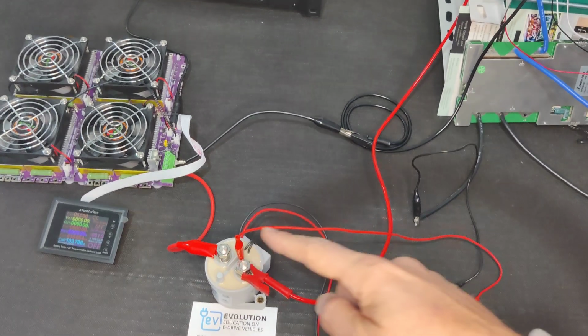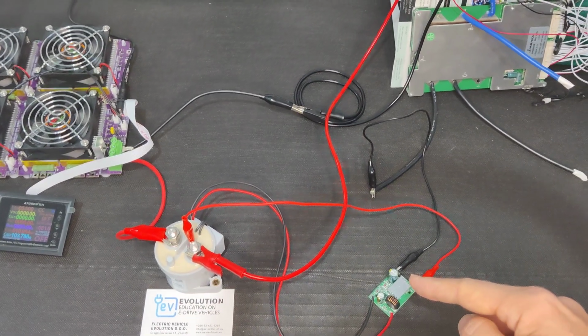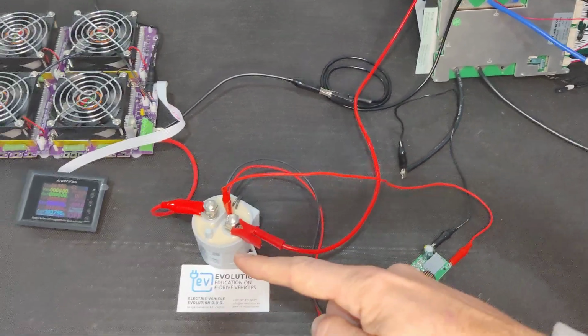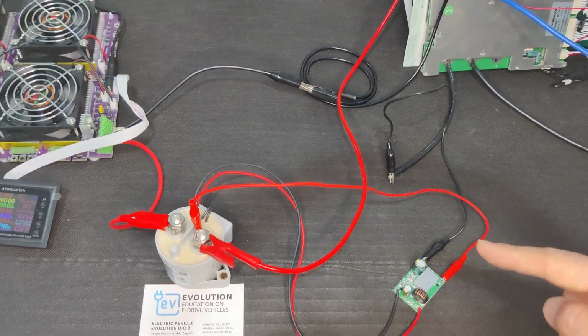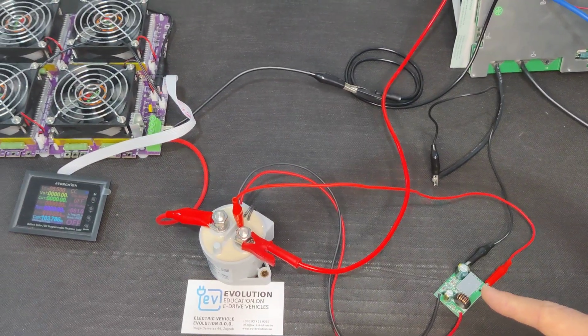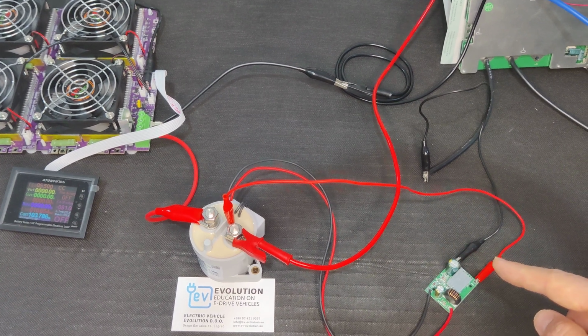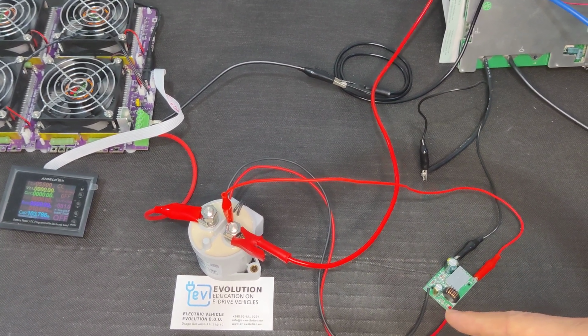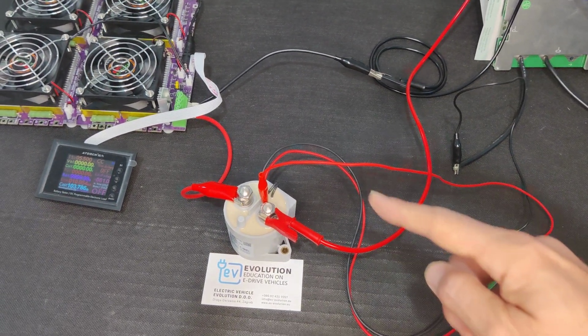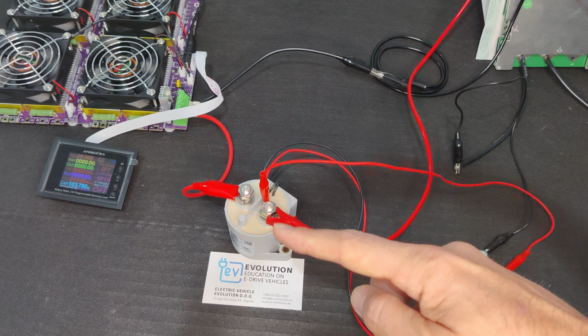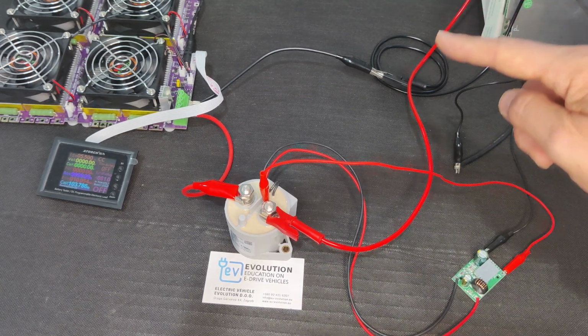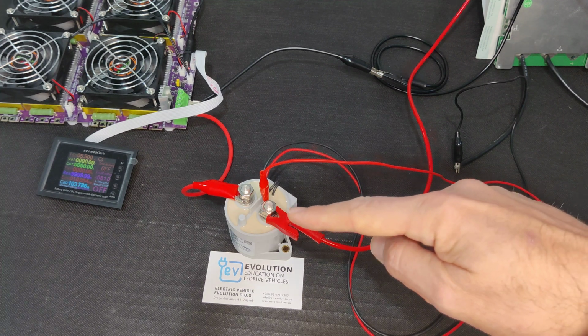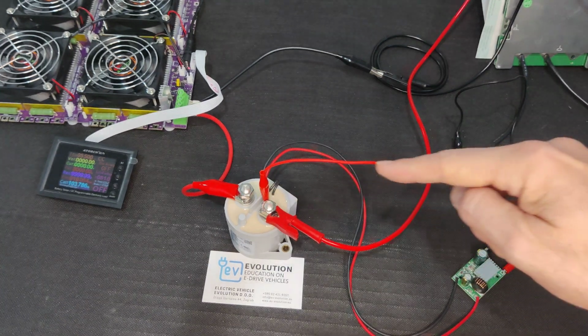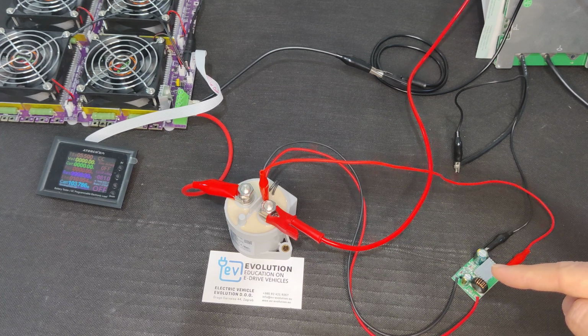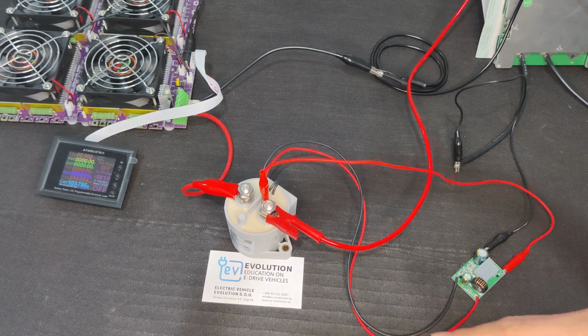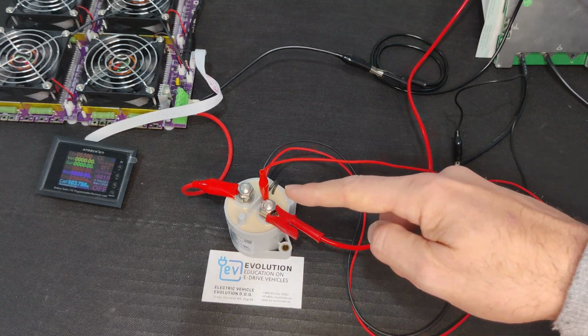From the relay we have a thin wire that goes to the power supply, which is a power supply for the relay itself. This power supply is for the relay. It's powered by 96 volts, and it transforms 96 volts to 12 volts, which is used to power the coil of the relay. So we have incoming 96 volts positive going with the thin wire to the power supply itself, and from there 12 volts goes to power the relay coil.